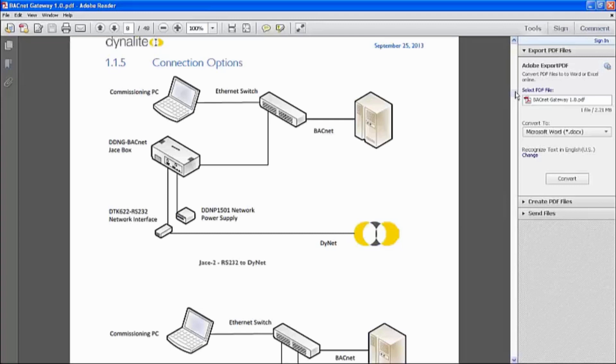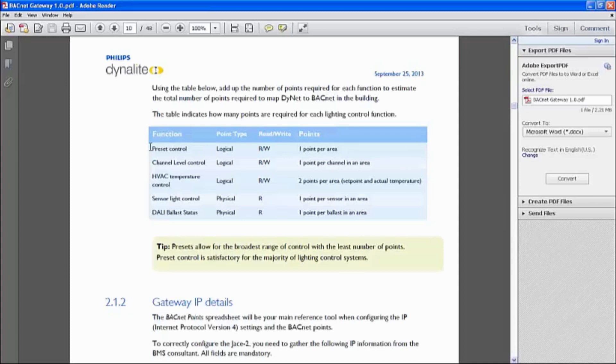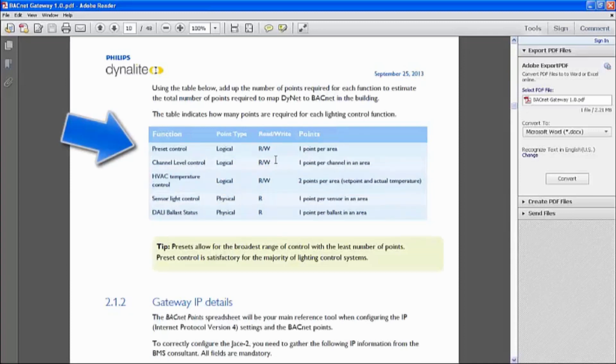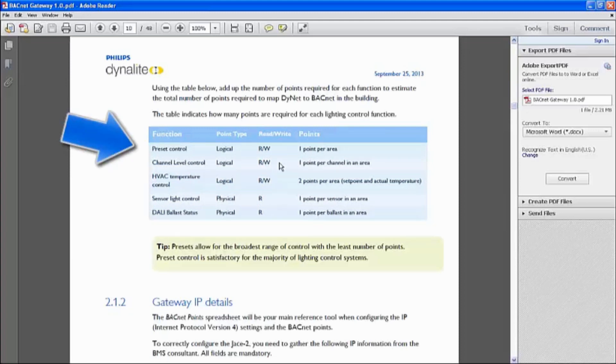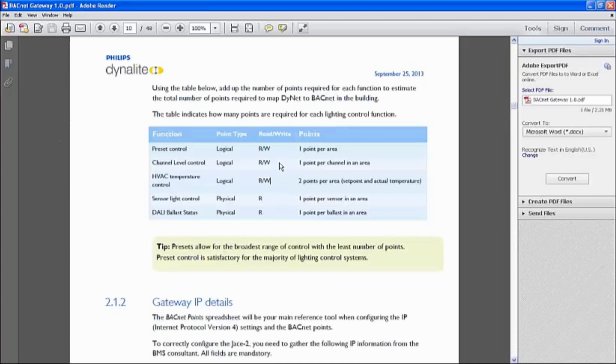So the points that we currently support, or we can call it opcodes that Dynalite can support, are currently this. Note that there's a read-write status to each of the points, meaning that for preset control, channel level control, and HVAC control, we can do a read and write, meaning that BMS are able to send scene settings and update on the Dynalite network and vice versa.